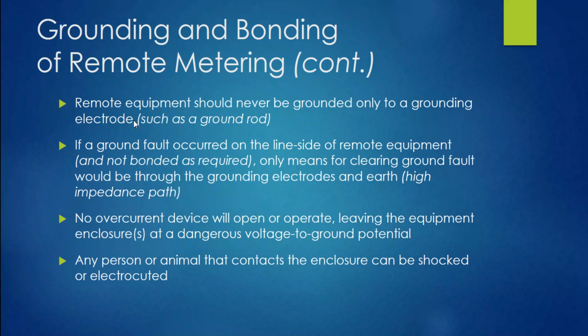Okay? I could drive a ground rod there, and I have to have my grounding electrode system at the structure itself. But I can't get away with having it only at the remote system. That becomes a hazard because any fault current in the service equipment could go down through the grounding electrode conductor, or actually, if you didn't have one in the service, any of the equipment could actually get energized over onto the earth through any type of incidental contact, and it could try to come back through the earth, up through that grounding electrode conductor into the remote meter, and it means that current's going to travel on a high impedance path. You're not going to trip the fuse possibly on the supply side or the primary side of the transformer.